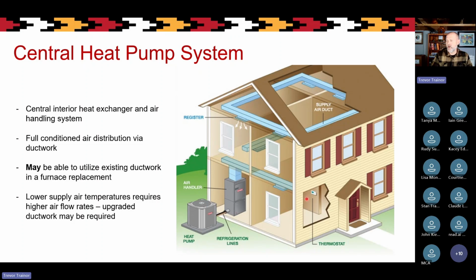You wouldn't really notice any real difference if you're living in the home. There are a few subtle differences in that the temperature of the air that's being supplied is a bit lower. So we need a bit more volume of flow to give us the heat to the different areas of the house. So you might notice that, but probably not. If you were replacing a furnace with a central air source heat pump, you may be able to use the existing ductwork, but that will have to be checked by a mechanical designer, because depending on the flows, you might need extra airflow, which might mean you need to update or upgrade or upsize your ductwork a little bit. That's because the lower supply air temperature requires a bit more airflow to get the heat where it needs to be.